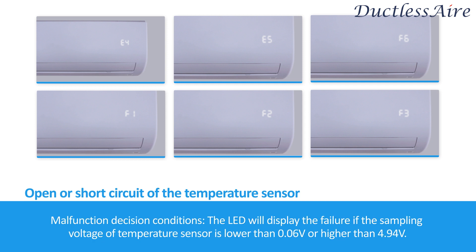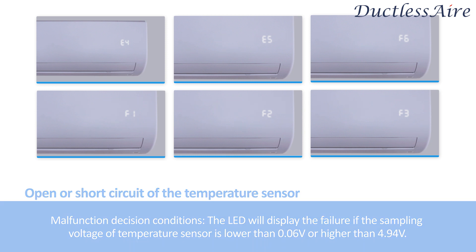Malfunction decision conditions: the LED will display the failure if the sampling voltage of the temperature sensor is lower than 0.06 volts or higher than 4.94 volts.